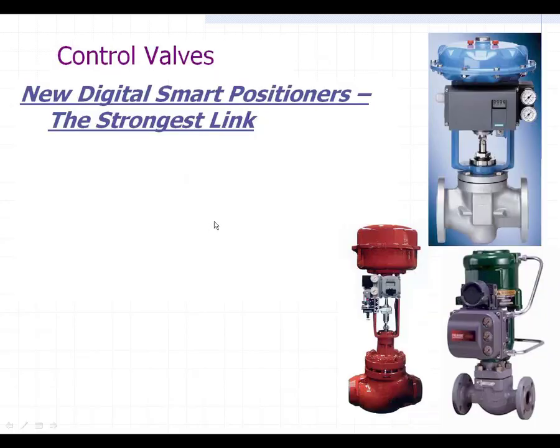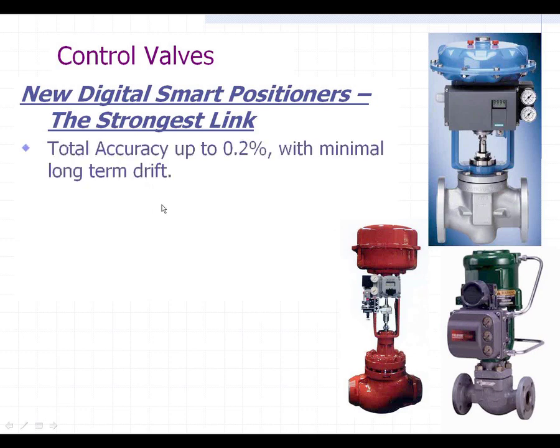Several manufacturers are making what's called smart positioners right now. These are the three leaders in the industry: the Siemens PS2, the Masoneilan Smart Valve Interface, and Fisher's Field Vue. All three are very good smart positioners with pretty much the same types of features. The accuracy of these is 0.2%, with minimal long-term drift — a whole lot better than the 5 to 10% we were talking about before.